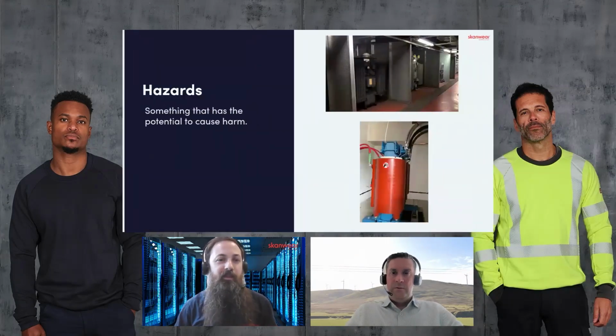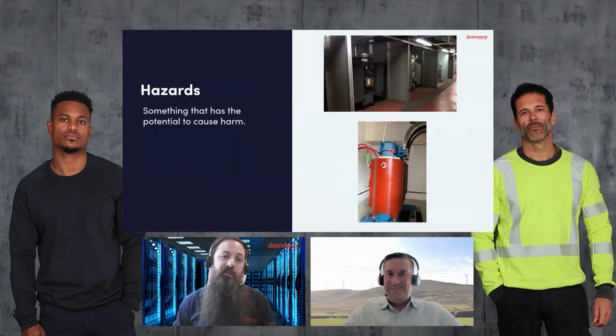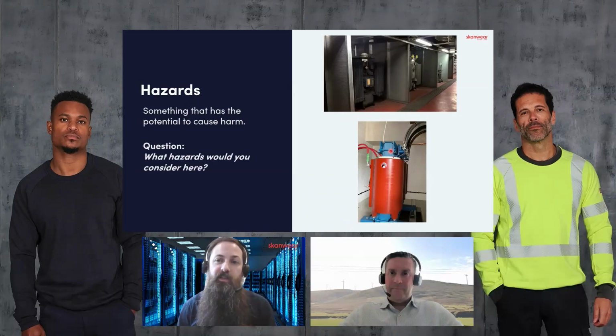Thank you. So these are two indoor transformer compounds. One's got fluid-filled transformers - I think there's a mix of mineral oil and synthetic oil - and then we've got a cast resin or dry transformer at the bottom, which I think is in Europe. That one's inside an indoor compound, but the door can be opened anytime. It's not interlocked with the switchgear, so that's an exposed conductor risk when you're opening the door, right in front of you.